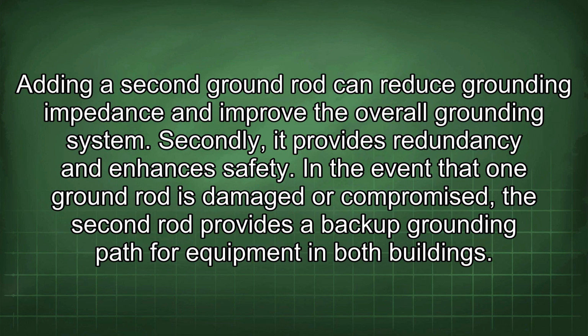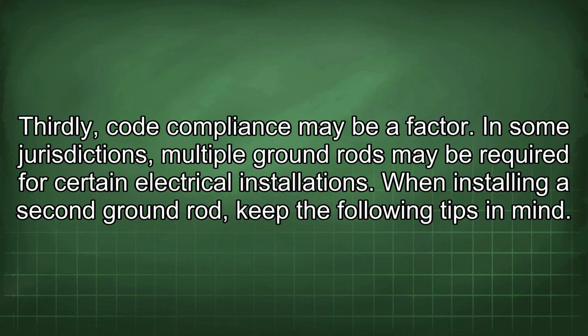In the event that one ground rod is damaged or compromised, the second rod provides a backup grounding path for equipment in both buildings. Thirdly, code compliance may be a factor. In some jurisdictions, multiple ground rods may be required for certain electrical installations. When installing a second ground rod, keep the following tips in mind.